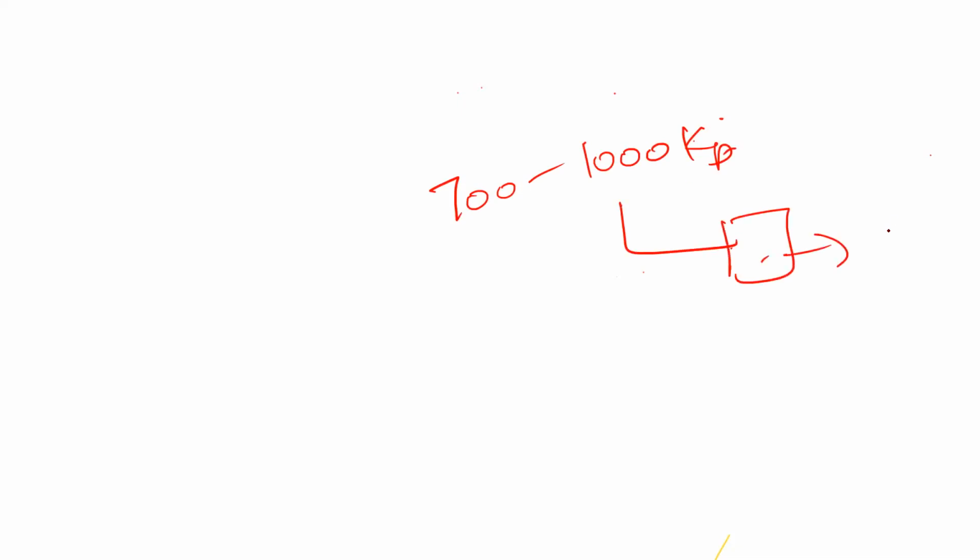Sir, can you just repeat the pressure regulator pressure once again, please? The pressure regulator, like the one we have in the manifold room. It comes at 700 to 1000 kilopascal in the pressure chamber, goes to the pressure regulator, and is reduced to 400 kilopascal or 55 psi. Okay.